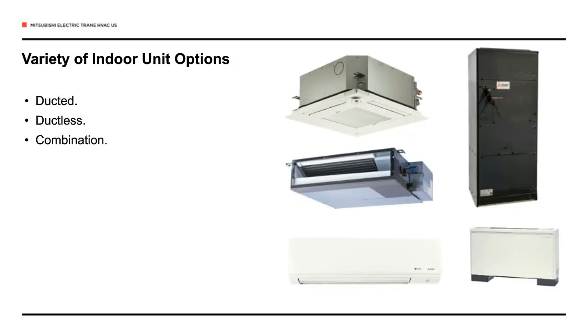As you can see here, there are a variety of indoor units from ducted to ductless, or they can be used in combination. VRF equipment is very compact, saving space and offering a variety of aesthetic choices. Here, for example, you can see the ceiling cassette, the ceiling concealed ducted unit, a wall-mounted unit, the air handler, and the floor standing unit.